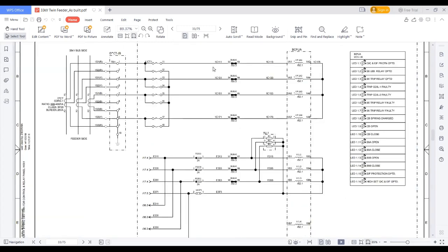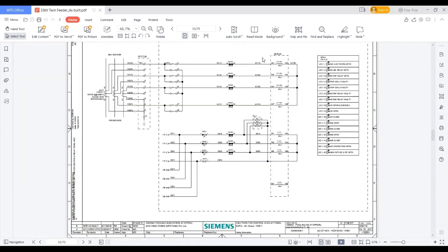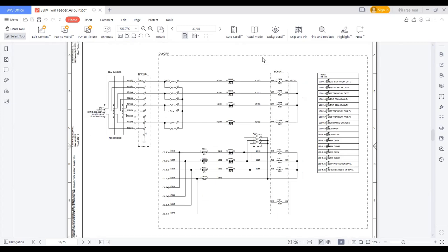So 5P20. So I said C. C represents protection. A ferrule C represents protection. So this is a protection, which should be connected to the relay. In our case, the relay is an inbuilt feature of the BCPU. So I'm directly giving this to the BCPU. That's it.